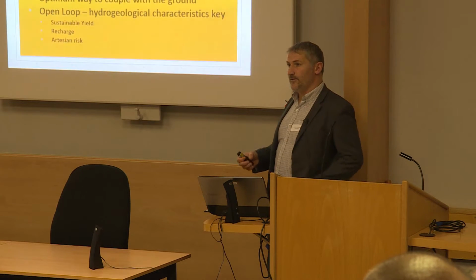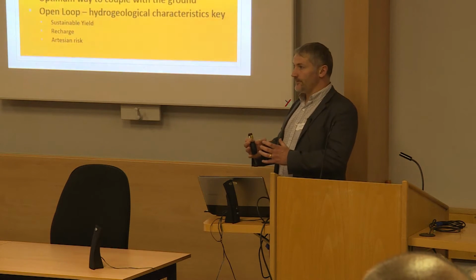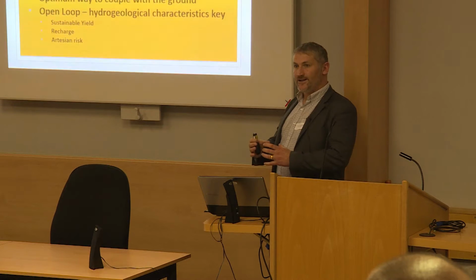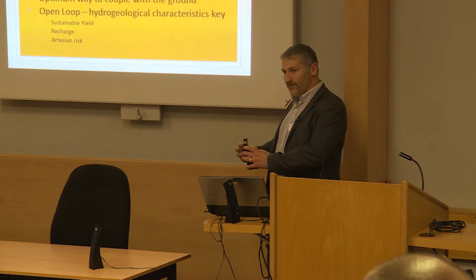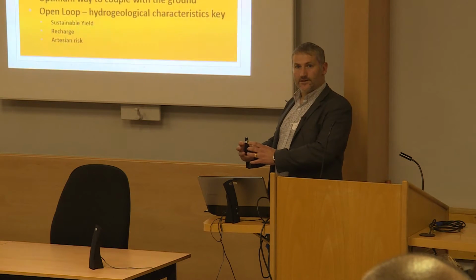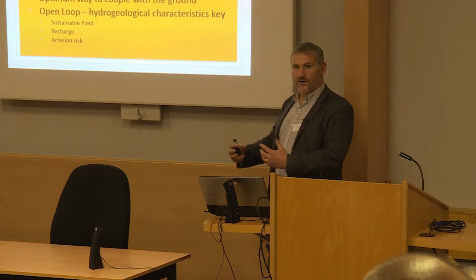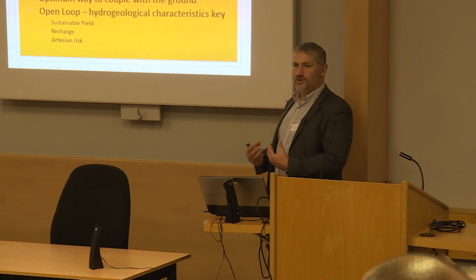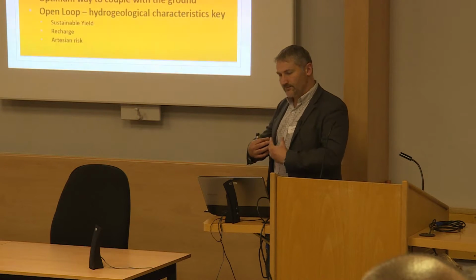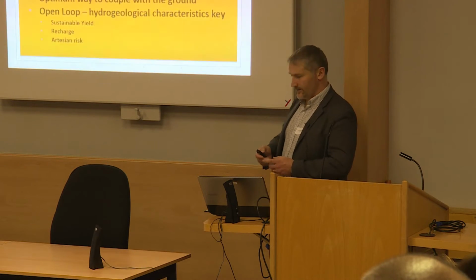You also need to know the specific heat capacity of the ground. That's effectively saying for this chunk of rock, a known volume, this is how much energy it takes to change that volume of ground by 1 degree Celsius. Because what we're doing is cooling the ground, making that warmth come towards the borehole, or making the heat go away from the borehole in cooling mode.